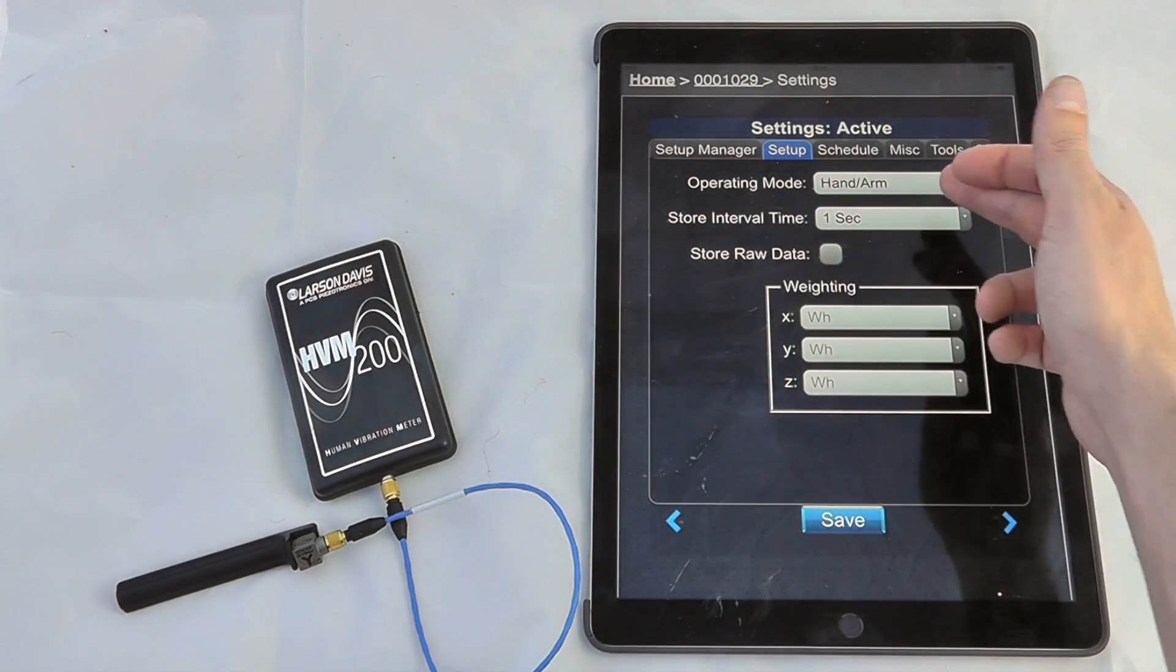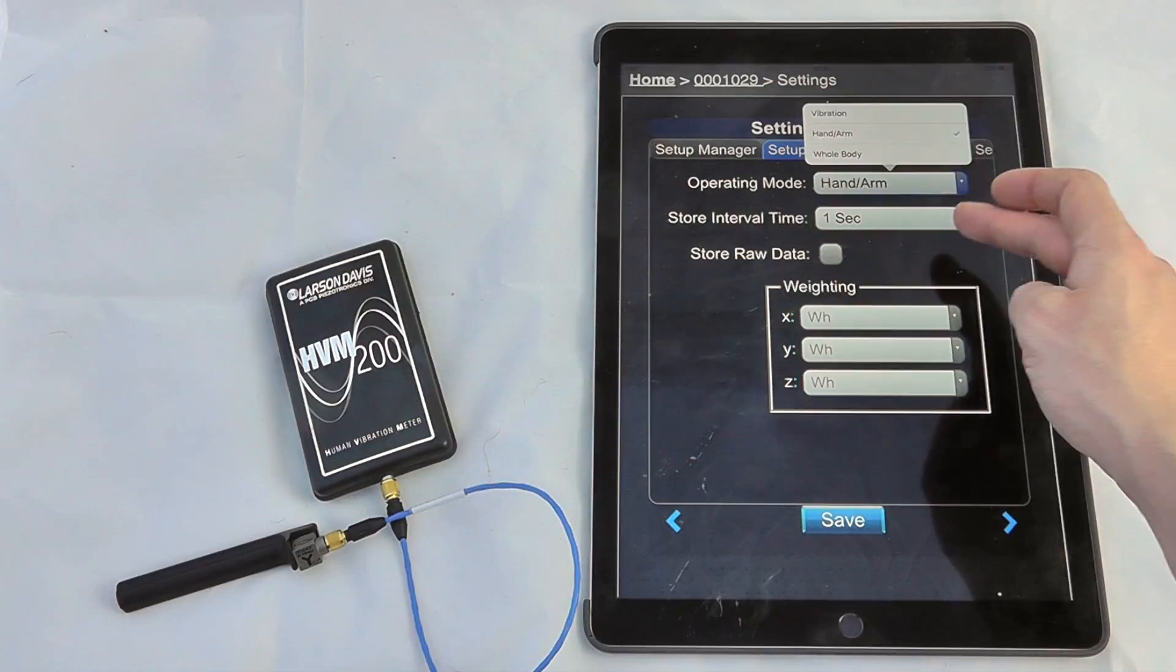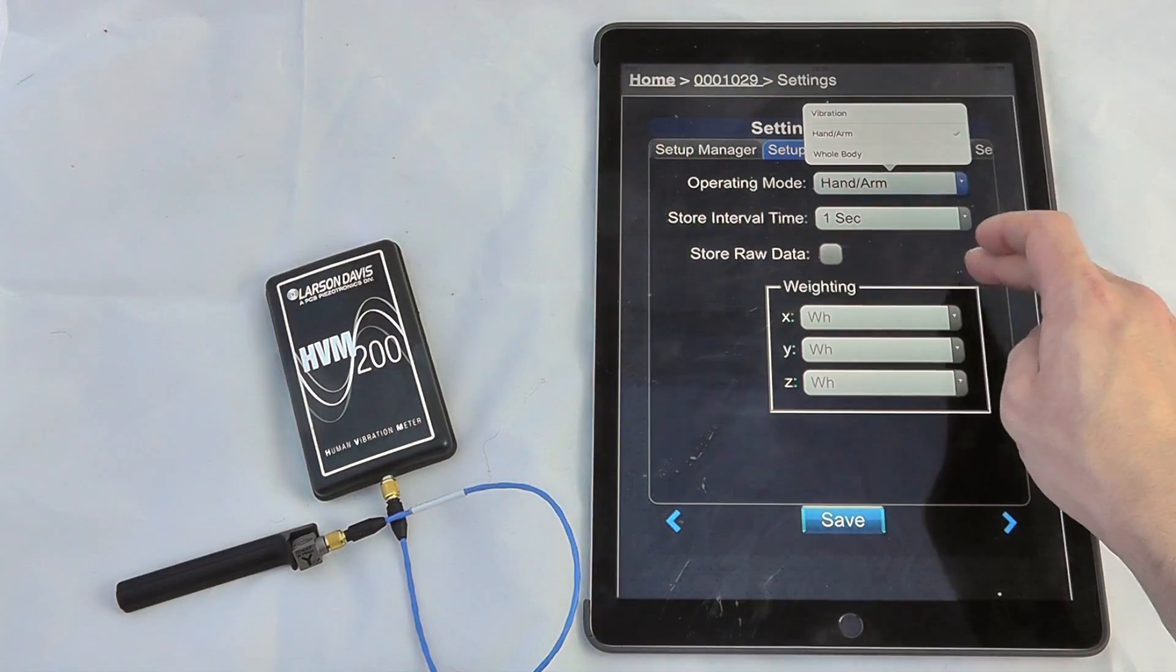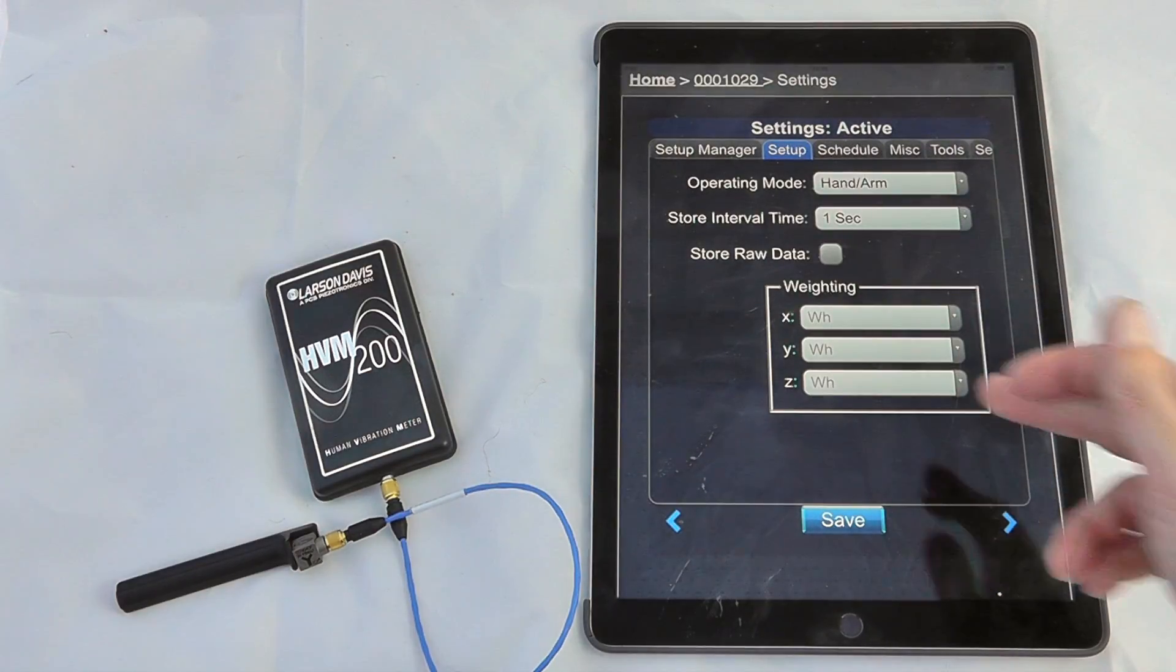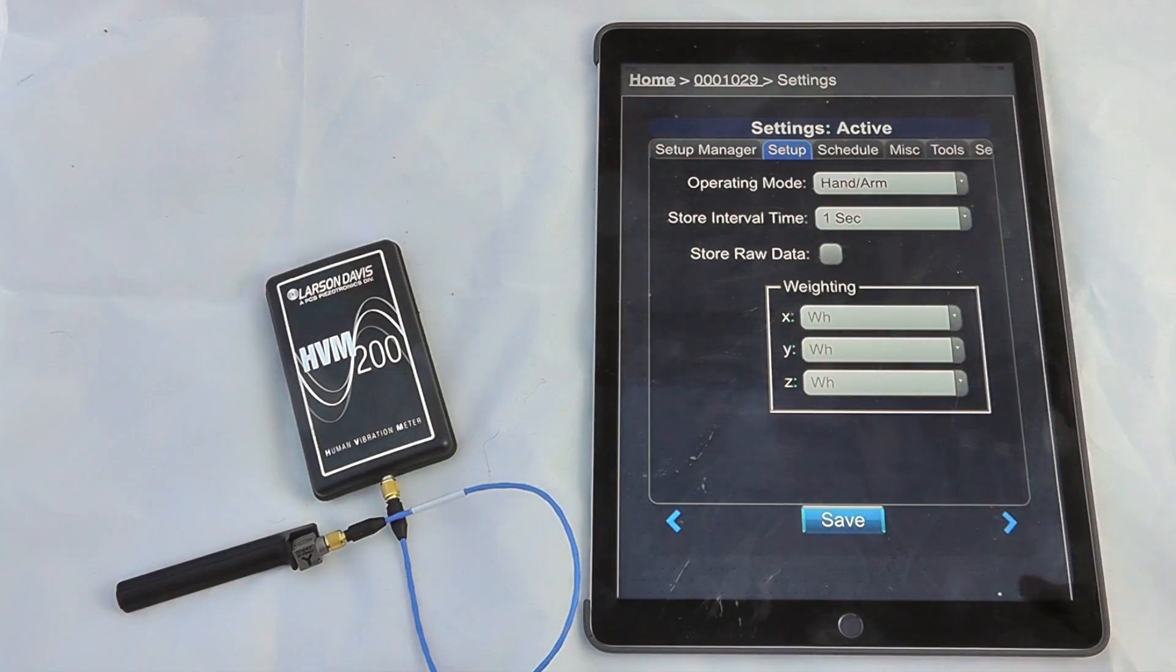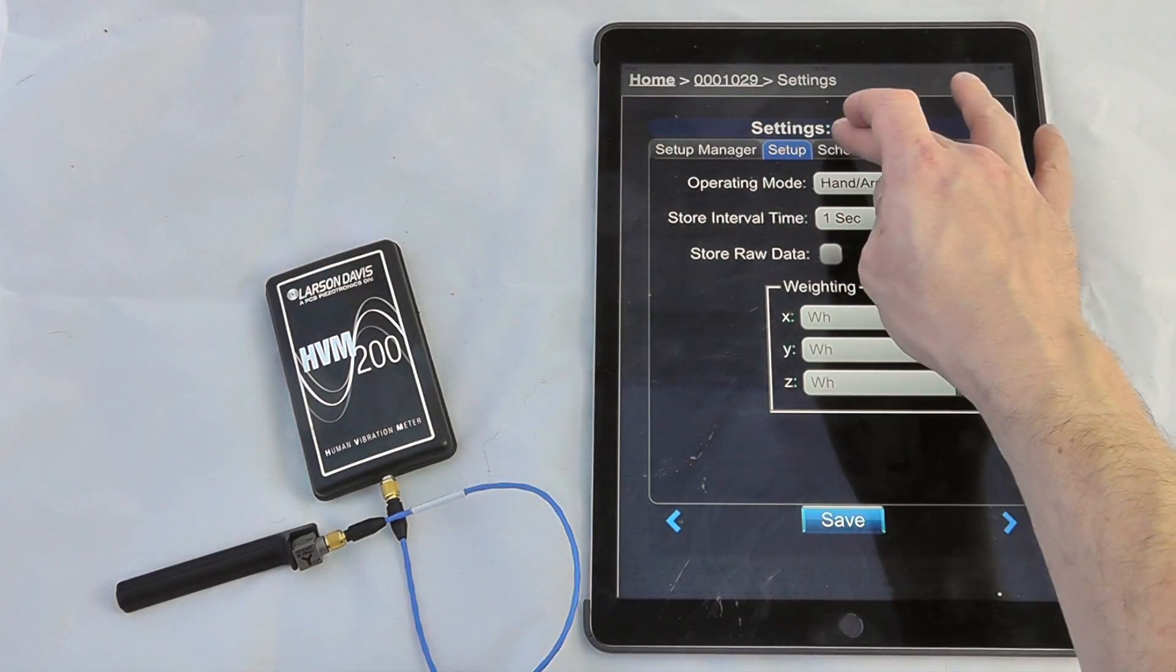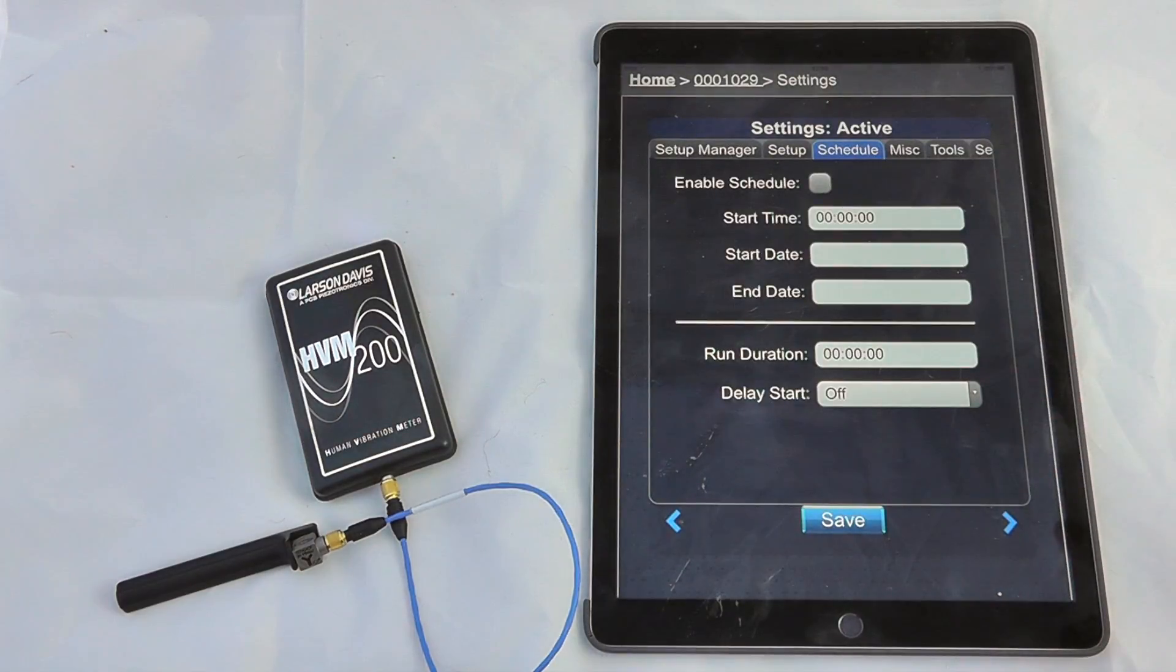We can look at the operating mode, be it hand arm, whole body, or general vibration settings, our storage and interval time, whether we want to store any of the raw data to interface with things like MATLAB, etc.